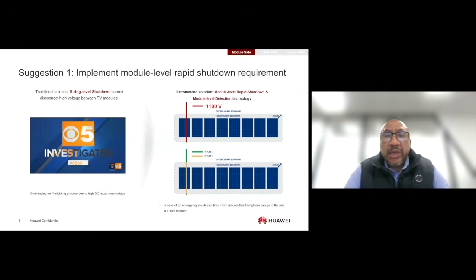So the first suggestion we want to look at is the rapid shutdown requirement. I know that Hein has touched on this before, where we have certain issues around the inability to disconnect high voltage between PV modules, especially during irradiated periods. We can then move towards a rapid shutdown facility that will ensure that outside of the array boundary, we have voltage levels that are safe for humans, and that will facilitate, for example, firefighting incidents, where firefighters need to access certain areas safely without compromising the ability to actually save lives.